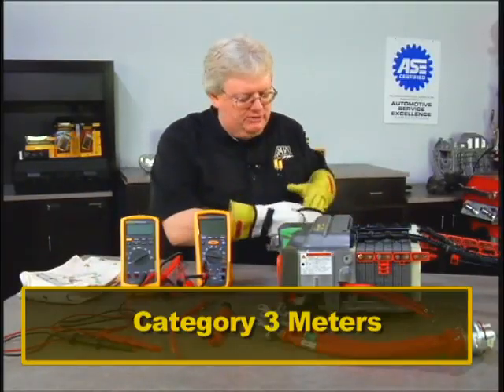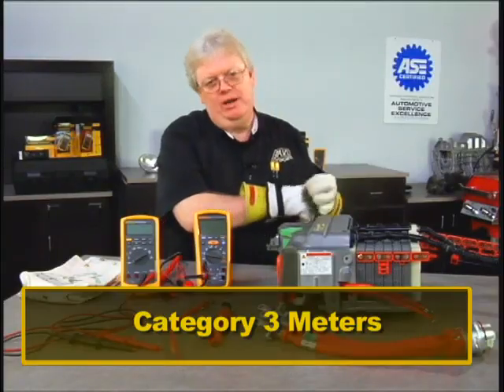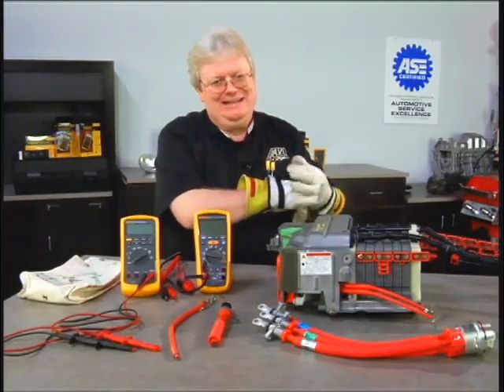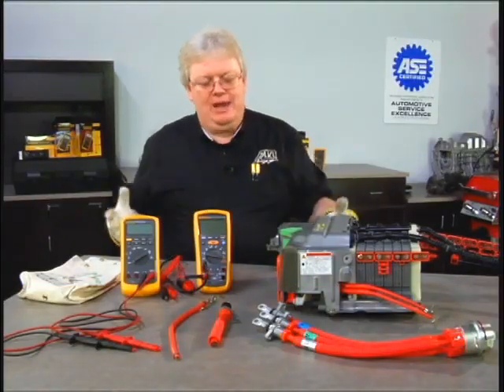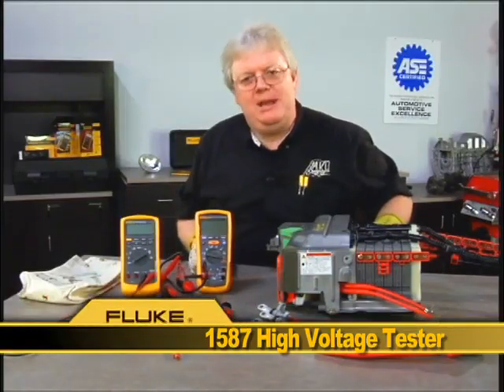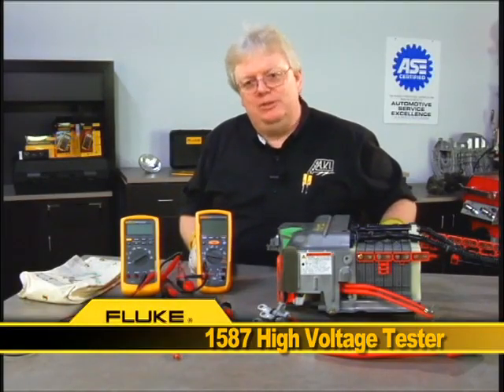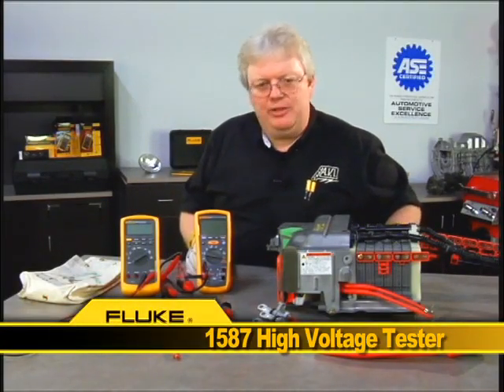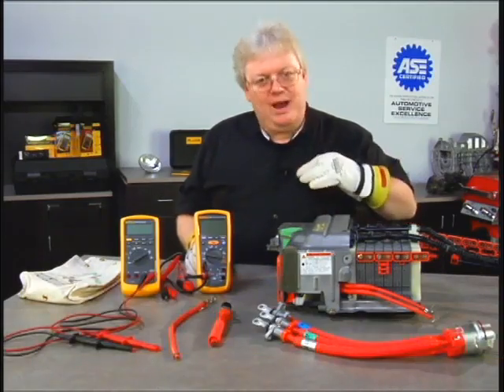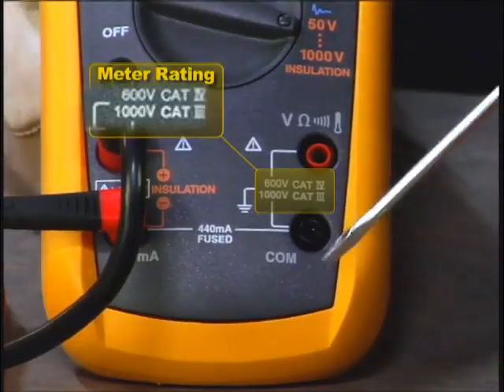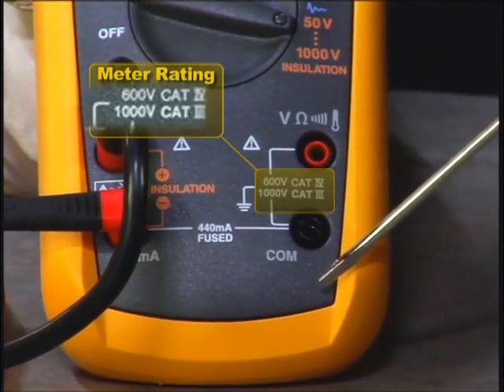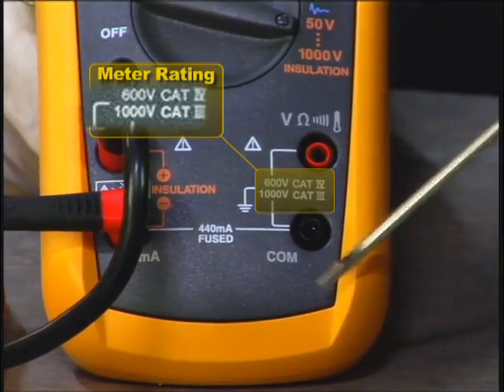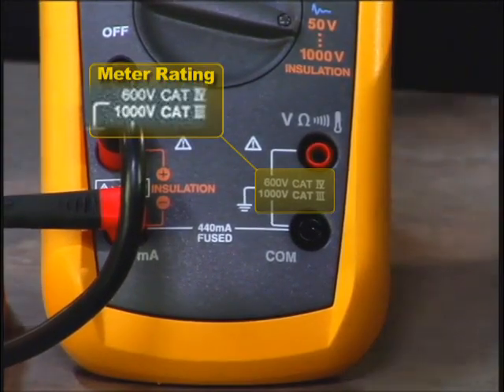Now, most of the Fluke's products are category 3 now. The 5 series, 87s, 88s, they're all category 3, and of course this Fluke 1587 high voltage insulation tester, also CAT III, 1000 volt meter. You can find the rating of that meter down here in the lower right hand corner of all the products. No matter what brand of meter it is, it will say whether it's CAT III, 1000 volts or not. This is actually CAT III, 1000 volts and CAT IV, 600 volts.